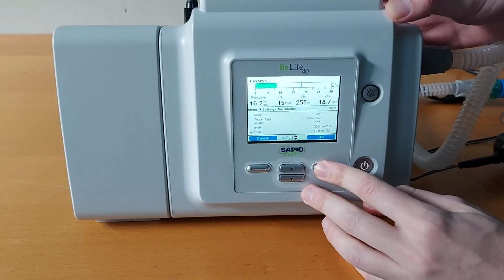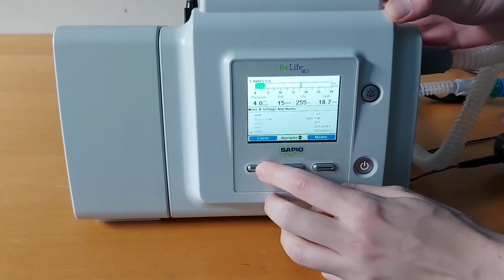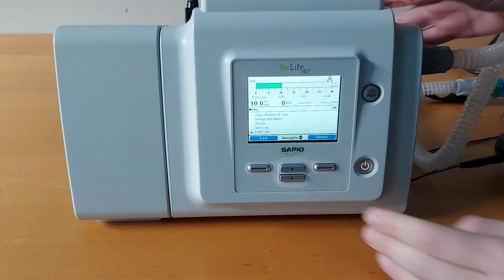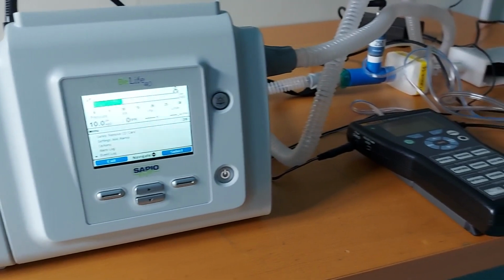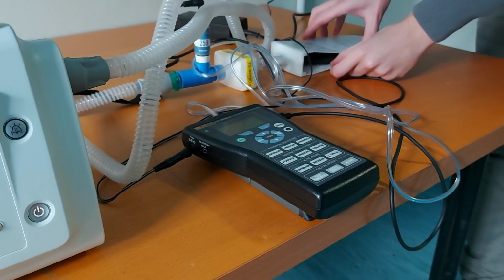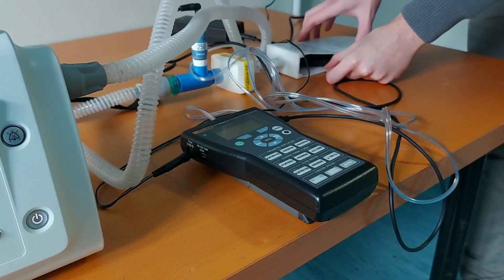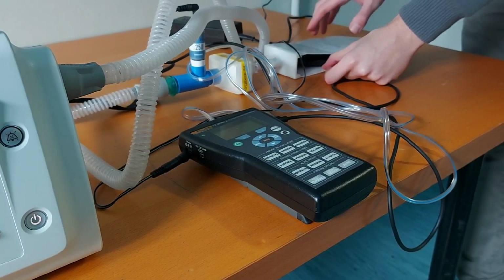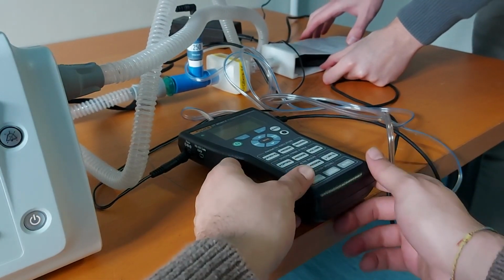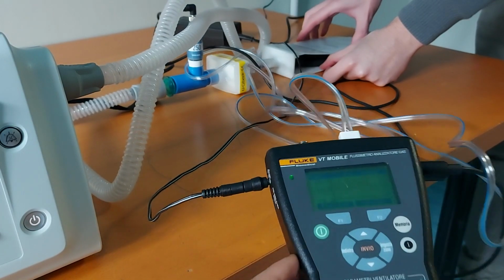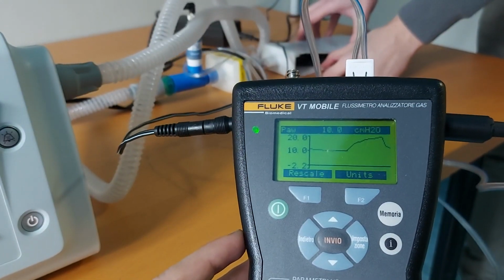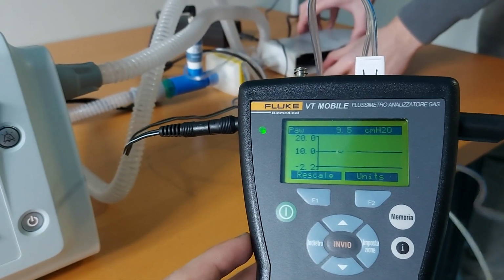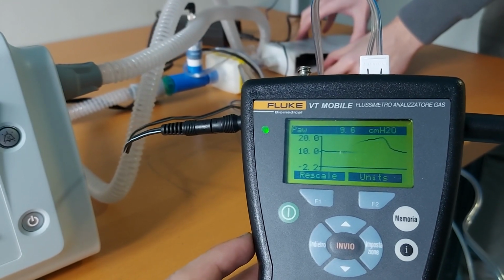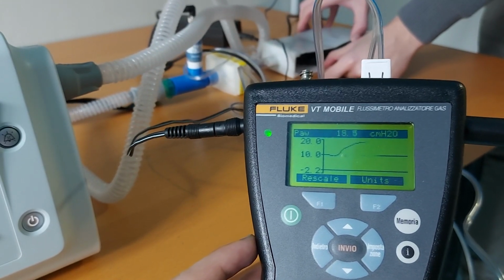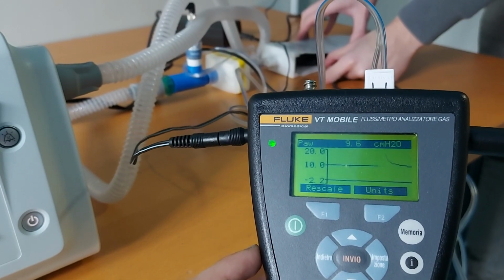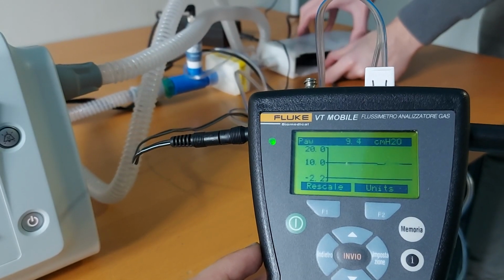To check the spontaneous or timed mode, simulate spontaneous breaths by expanding the bellows of the test lung. Verify that an assisted breath is delivered in response to a breathing effort when the breathing circuit exceeds the sensitivity setting. Verify that an assisted breath is delivered within the set time when the sensitivity trigger has not been exceeded. Also, verify that the unit maintains the inspiratory pressure and expiratory pressure levels for the set times.